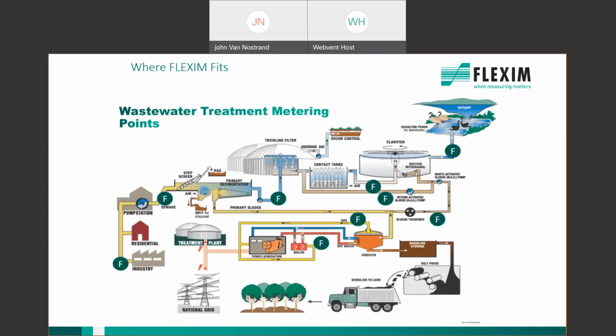Likewise, on the wastewater side, from the collections throughout the treatment process into the final effluent and all points in between, including chemical injections again, we have a lot of applications with dosing polymers, hypochlorite, and bisulfites. So any of these locations where you see the F is a great location for a FLEXIM flow meter.